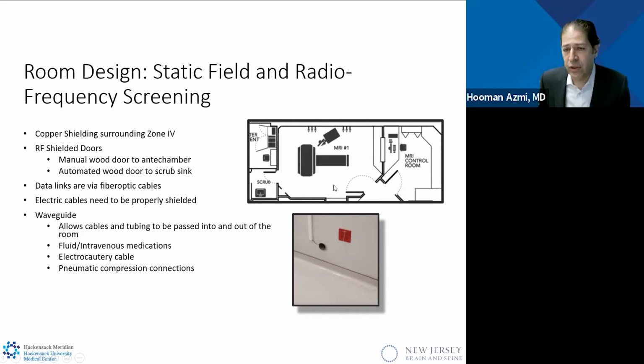The waveguide, which most MRIs have, is basically a conduit through the copper shielding. But it was very important for us because some of the equipment we use is not MRI compatible, and we needed a way of bringing that material into the MRI. For example, bipolar electrocautery. We use it, but the machine is outside and we run the wires through here. And our pneumatic compression device for the legs. Also, the machine is MRI incompatible, but the tubing is all plastic. So we run the tubing through here. So that's a very critical part of our design.